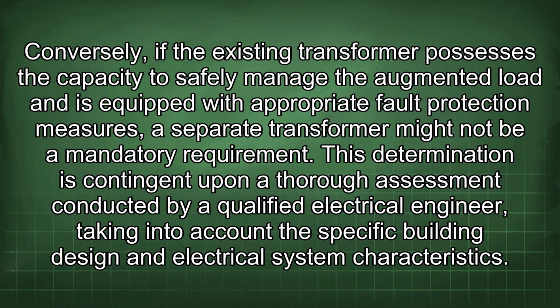Conversely, if the existing transformer possesses the capacity to safely manage the augmented load and is equipped with appropriate fault protection measures, a separate transformer might not be a mandatory requirement. This determination is contingent upon a thorough assessment conducted by a qualified electrical engineer, taking into account the specific building design and electrical system characteristics.